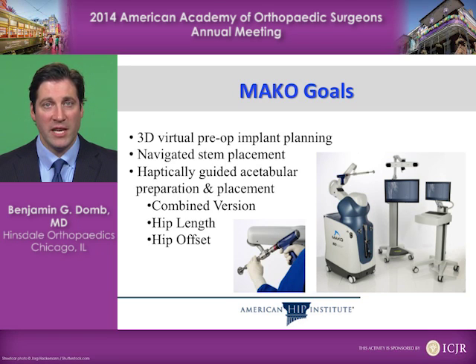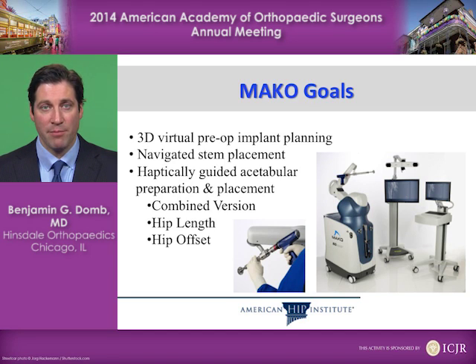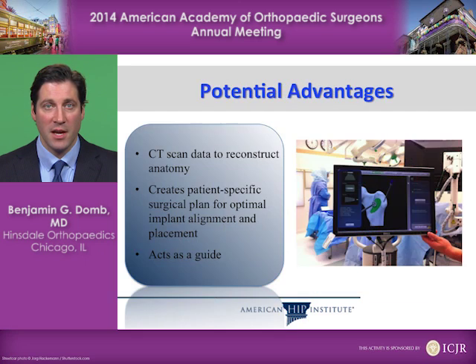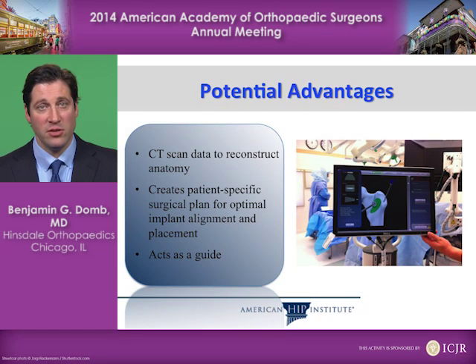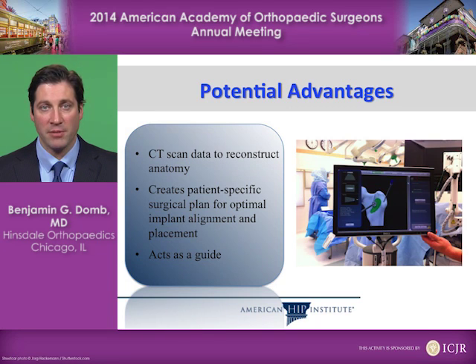The robotic system uses a 3D virtual pre-op implant planning system, a navigated stem placement, and haptically guided acetabular preparation and placement. It allows us to assess combined version, hip length, and hip offset. Potential advantages include the use of CT scan data to create a virtual model of the patient and a patient-specific surgical plan for optimal implant alignment and placement.